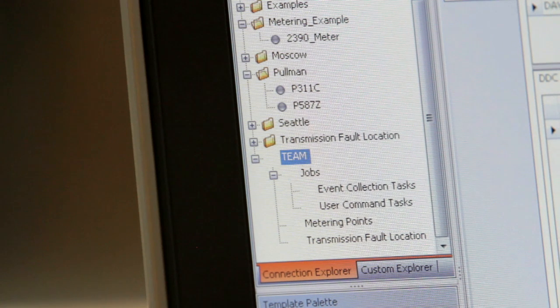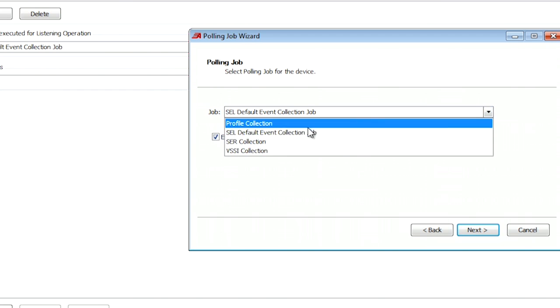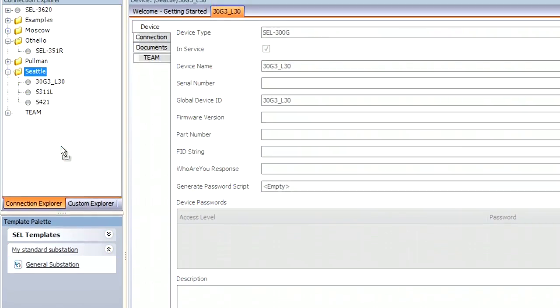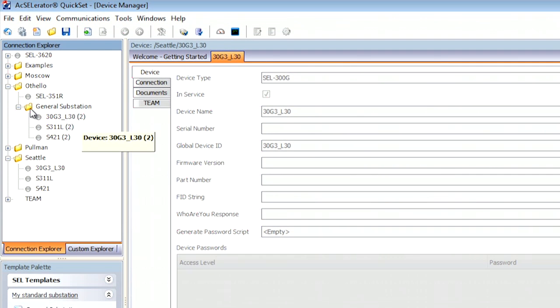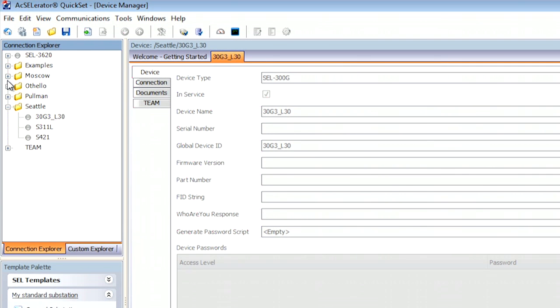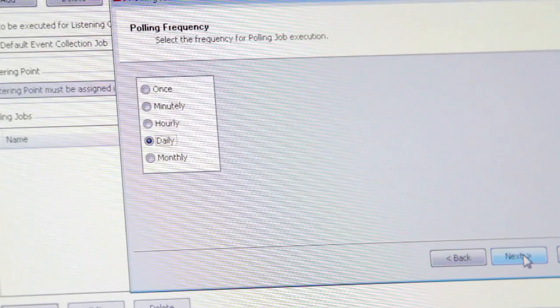TEAM has a very nice way of defining jobs within a system. These jobs can be anything from collecting event files or COMTRADE files, all the way up to collecting load profile data from our Schweitzer meters. Once these jobs have been defined, assignment can be anywhere from an individual device in the connection directory, all the way up to assigning an entire region to go out and collect events every five minutes, every week, or every month. This is all built into the configuration software with the end user in mind.